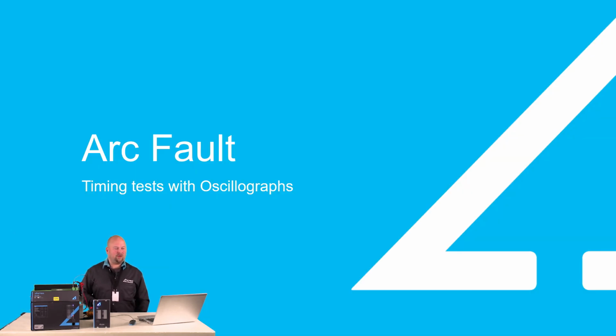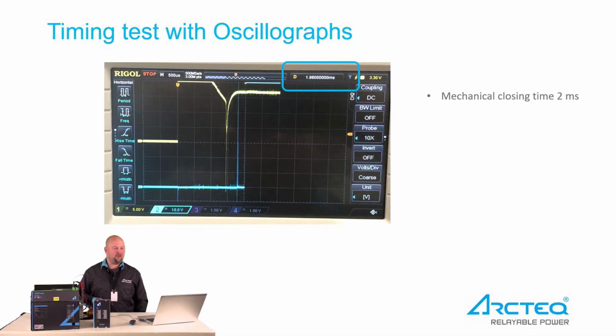Timing tests with oscillographs. Here, this is now a timing test. I just took this photo today from our production, and this is a timing test of the single shaft mechanical closing time, from the flash to the closed position. The mechanical closing time for this particular device was 1.98 milliseconds. So typically we can say that the mechanical closing time is 2 milliseconds.